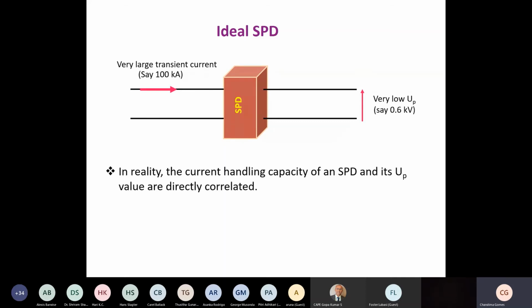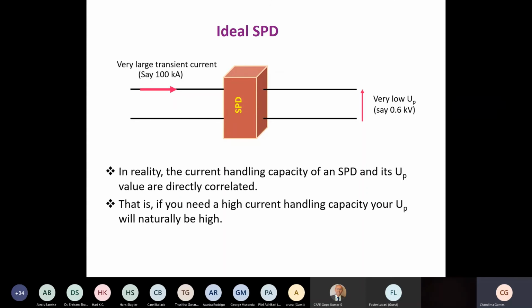But unfortunately, the current handling capacity and UP values of an SPD are directly correlated. What does that mean? When the current handling capacity increases, the UP value will naturally increase. So, for example, if you select a peak transient current of 3 kiloamperes in an SPD, its UP value may be 0.7 kV. But on the other hand, if you select a 50 kiloampere SPD, its UP value may be like 2.8 kV. Okay, there's a typing mistake there, 2.8 kilovolts.